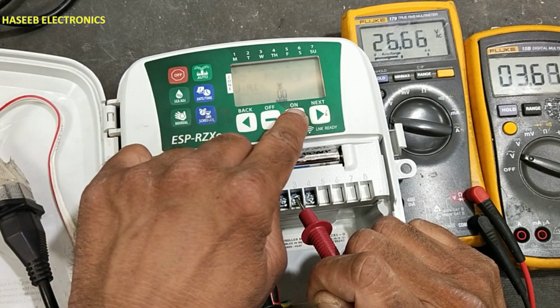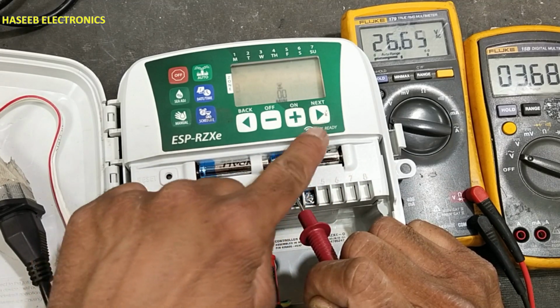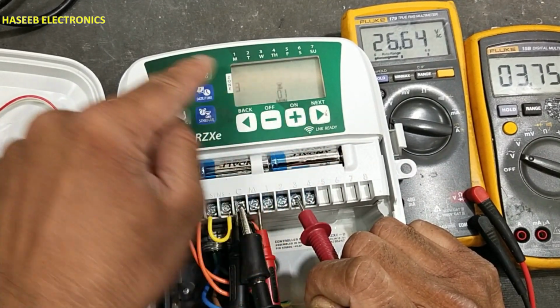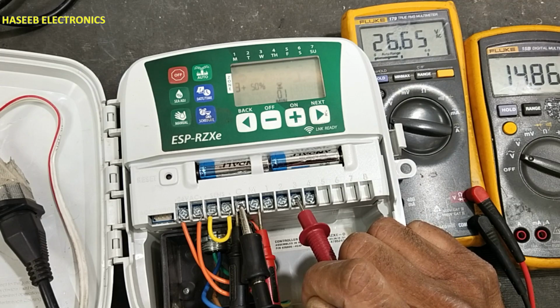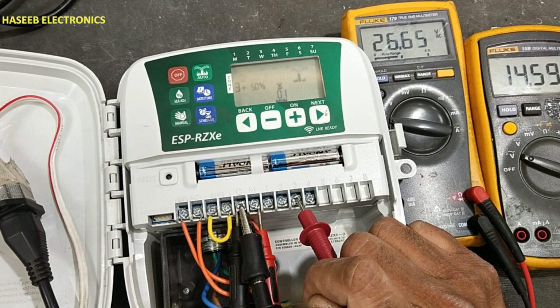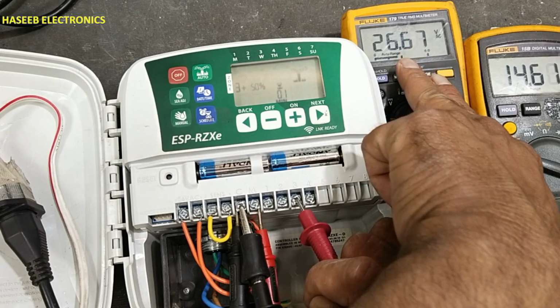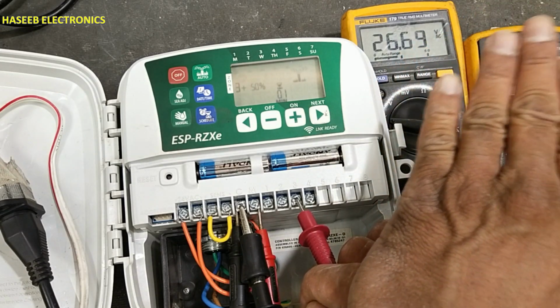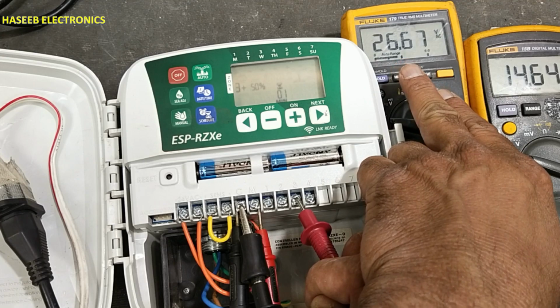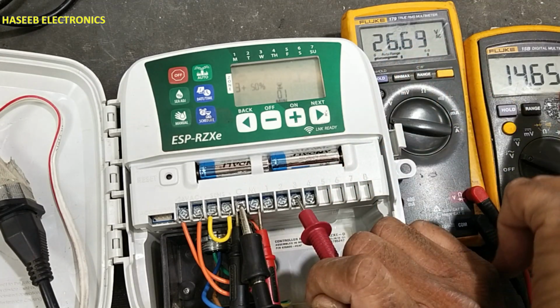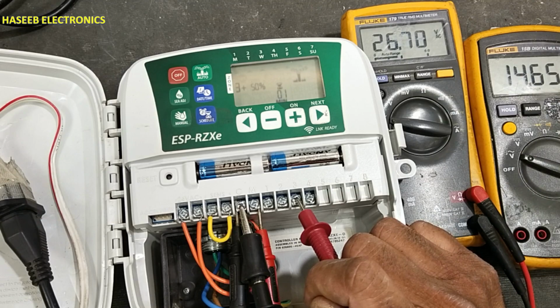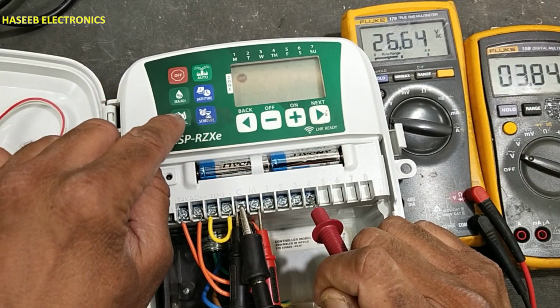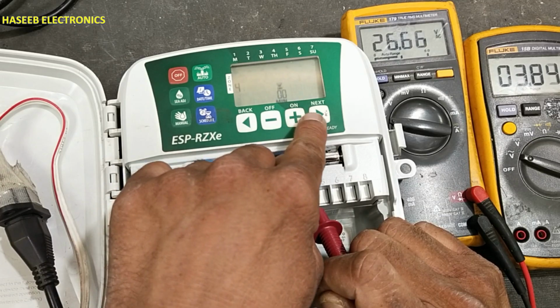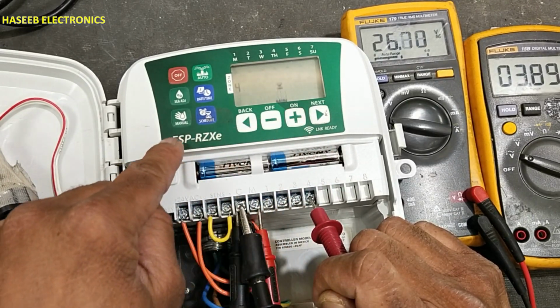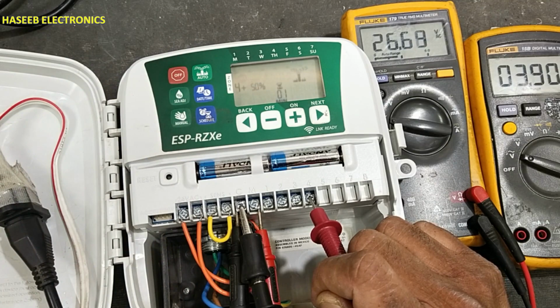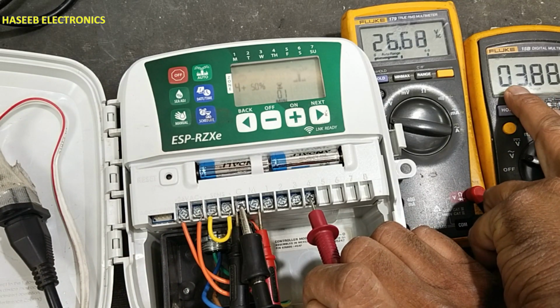Station number 3 for 1 minute on auto. It is 14 volt, not good. And this one is permanently pulled high, so it is providing direct output, which means something is wrong. Okay, station number 4, next, 1 minute auto. It is not changing output.